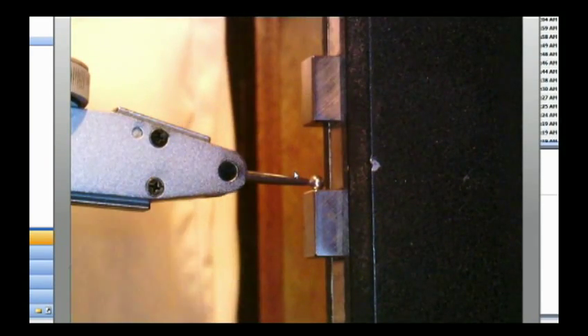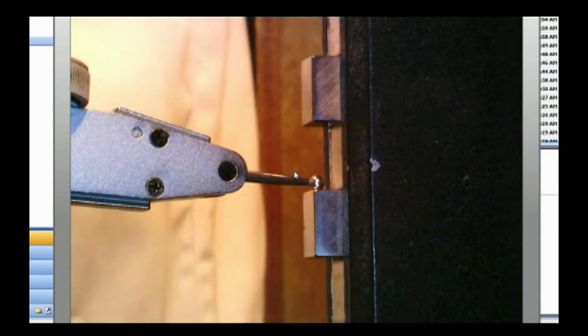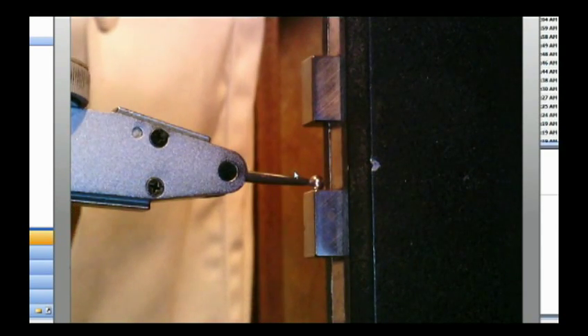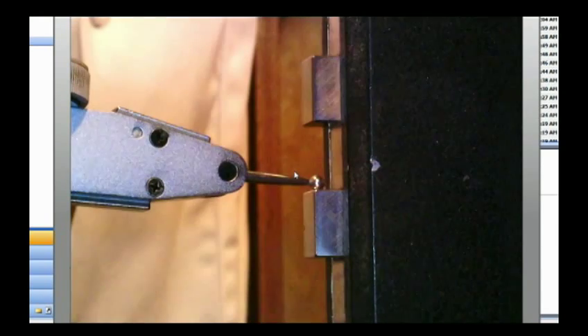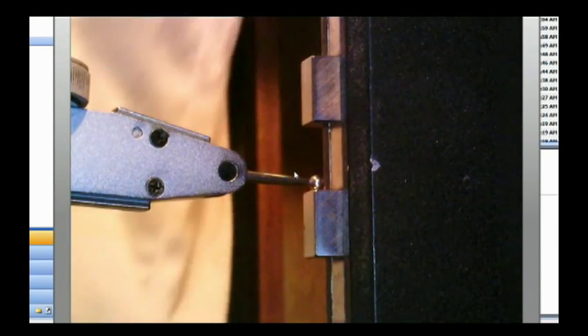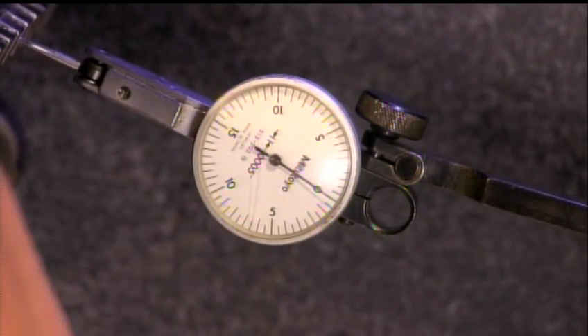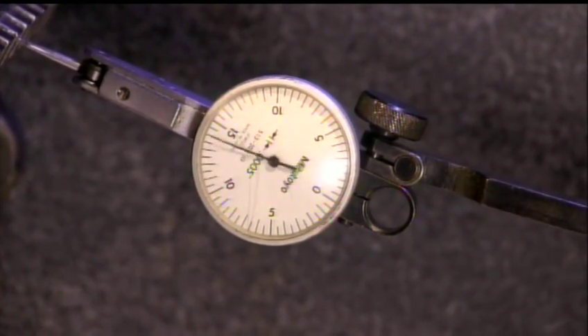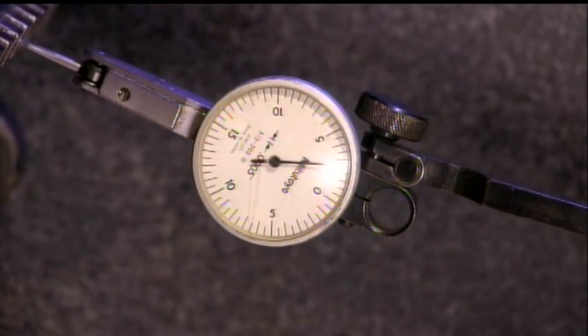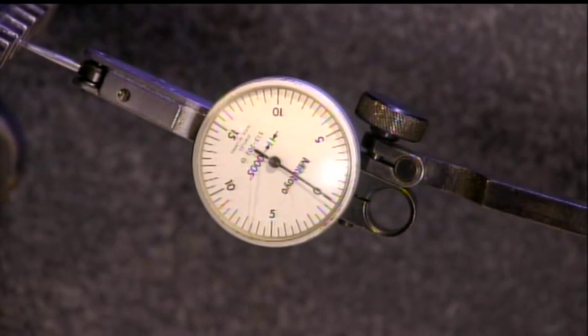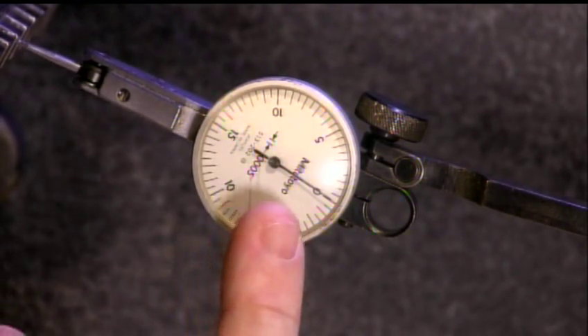Let me see if I can get a shot of what you're talking about there. Right here. Oh, there we go. So now we're on your indicator. I'm going to rotate and move that needle 30 thousandths. I'm raising my gauge block stack 30 thousandths, and it should read within one division, and it does. It's reading very close to one division. Just to reiterate what we just did, you moved your precision gauge block stack exactly 30 thousandths, and sure enough, the dial indicator read 30.